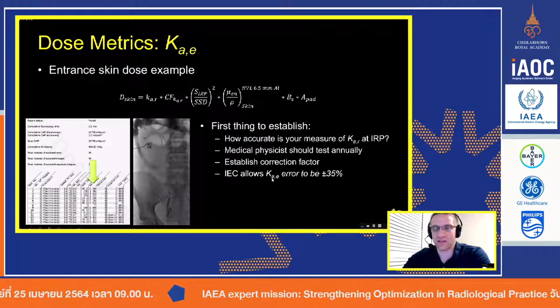Now, it's important to understand that the vendors, the manufacturers of all of your equipment out there, have a standard that they must meet to sell their equipment. There's an international standard that's defined by the IEC. They do not require the vendors to be any more accurate than 35%. So the value you see on that screen when you're operating could actually be plus or minus 35% accurate. Could be higher by 35% or lower by 35%. So that's why it's very important for the medical physicist to go in and verify that. In fact, they could verify it and correct it and make it more accurate on the display.